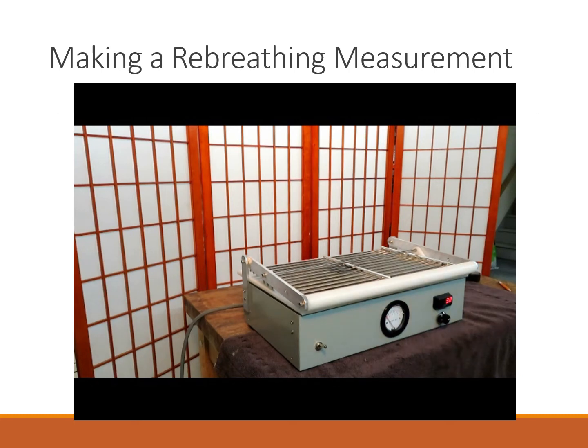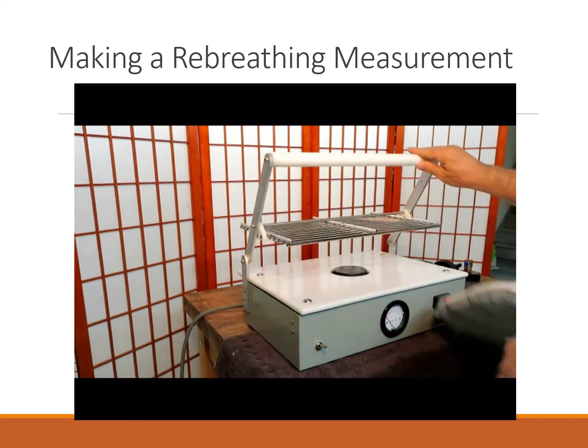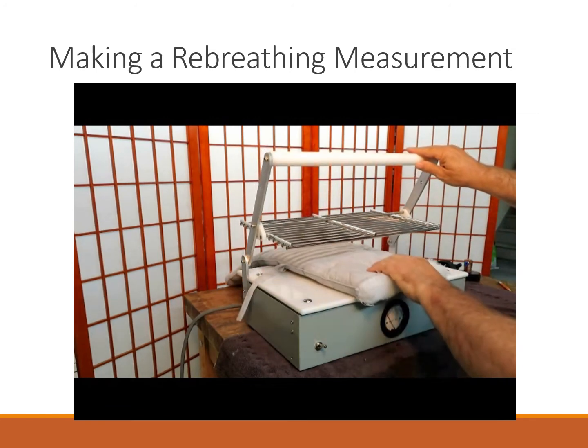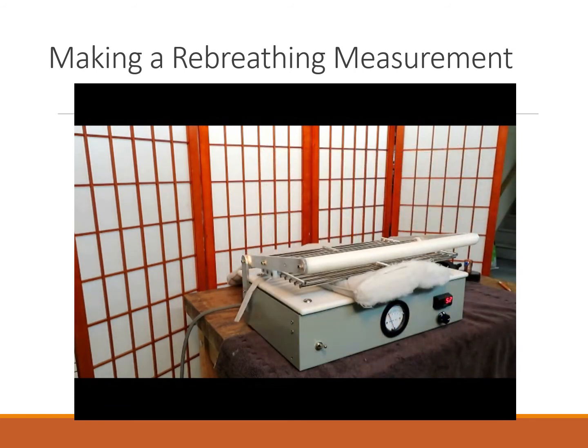And then after it's stabilized, after several minutes, the sample can be changed. So it can accommodate a range of sample sizes and thicknesses and measures two things. The indicator in the center is the pressure difference across the sample, and the indicator on the right is a measure of rebreathing.